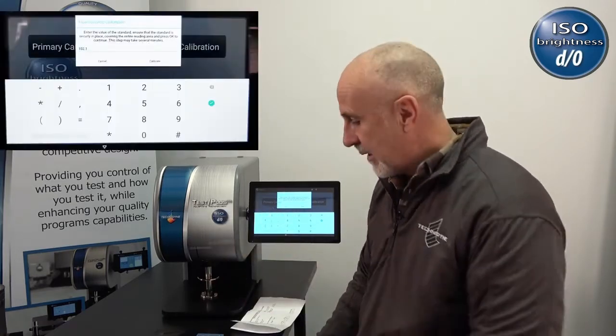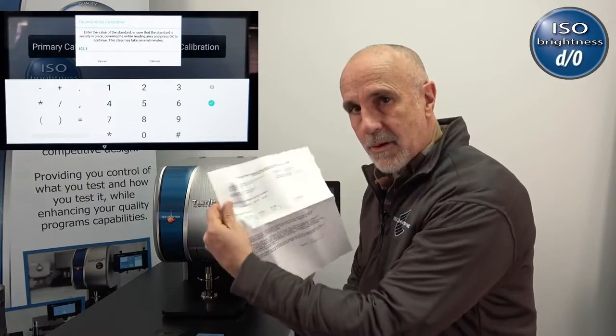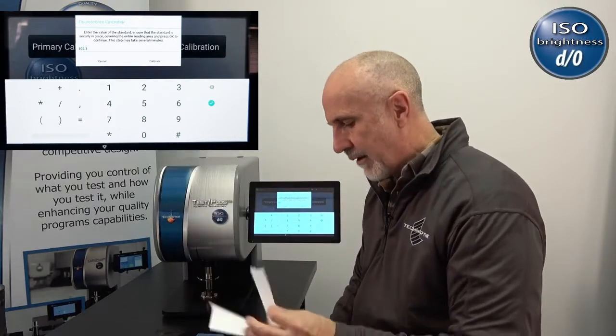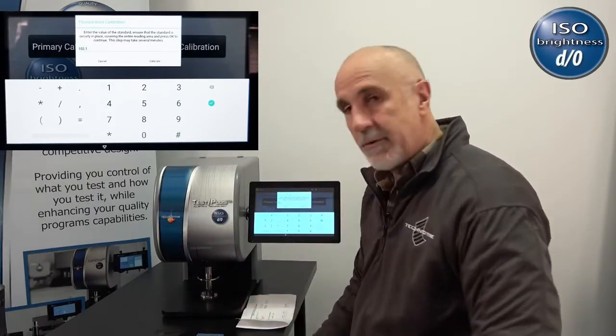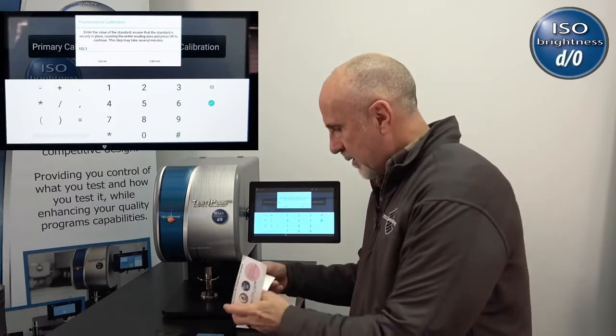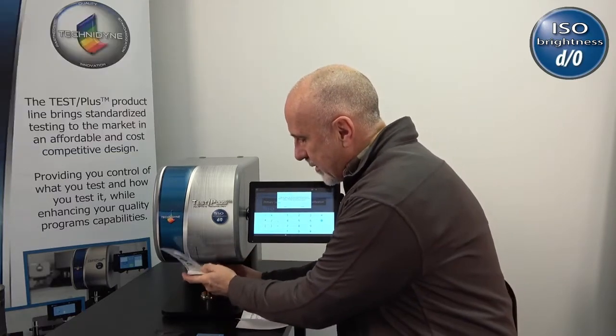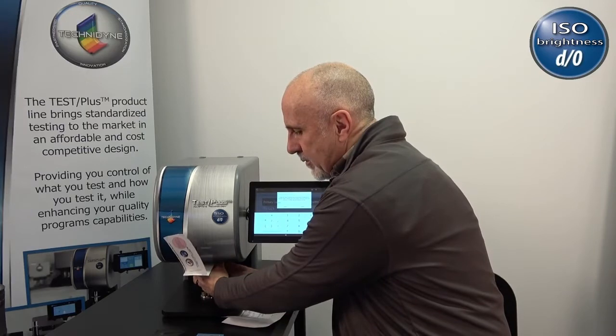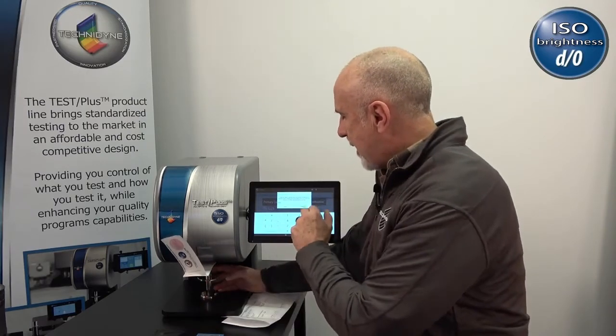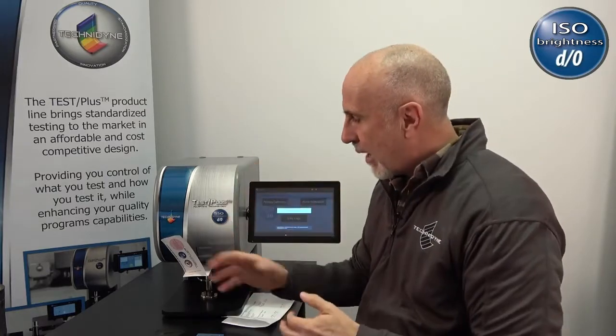Now the next thing it says is to load the fluorescent standard. The value for this is on the additional sheet of paper you have there, and for this standard it's 102.1. So I'm going to load that standard just like I did the other onto the instrument, and I'm going to hit calibrate. And in this sequence we're going to adjust the lamp voltage to where the UV energy is sufficient that we get the right fluorescent characteristics in that sheet to get the achieved brightness level you're looking for.